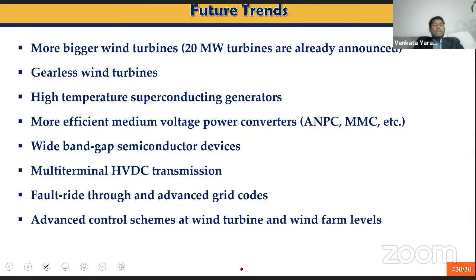Fault ride-through control right now is implemented by DC choppers, dissipating the surplus energy in DC resistors, but that is not an efficient method. Rather, it's going to be more advantageous to store that surplus energy. So having energy storage systems with each turbine or at wind farm level is going to be more advantageous than curtailing the output of the wind turbines to make it smoother.